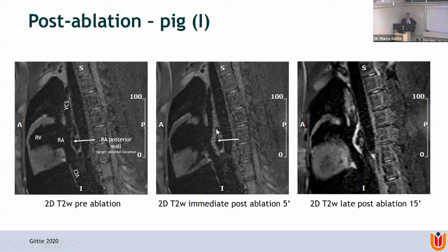there's an instant reaction, affected by this increased wall thickness due to the ablation. And there's also an increase in signal, reflecting the piling up of edema. You are aware of this as an electrophysiologist. If you position your catheter and you ablate, and you want to go back to that point, sometimes it's a little bit higher. You cannot tell the wall thickness, but the increase in wall thickness also affects the efficacy of your ablation. The penetration of energy is modified by the presence of edema.